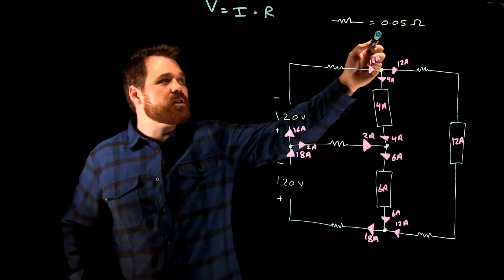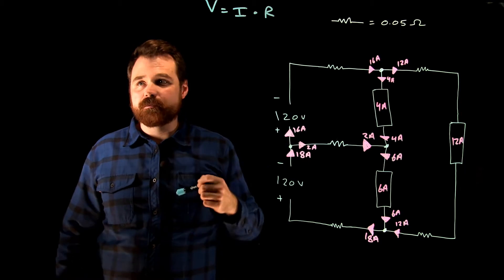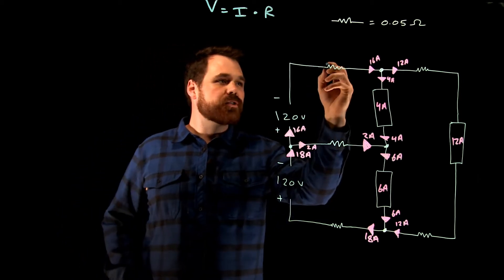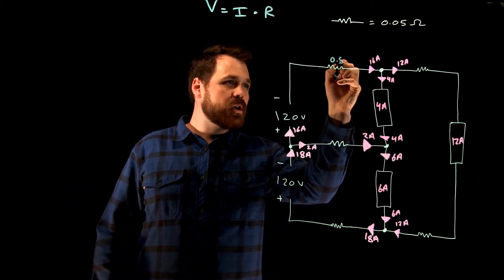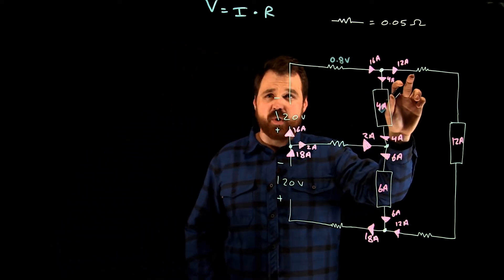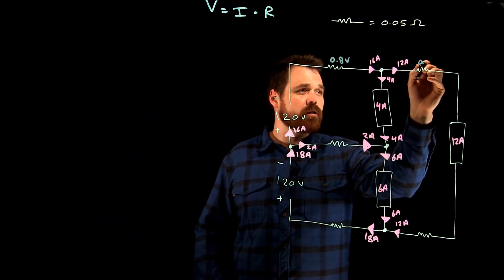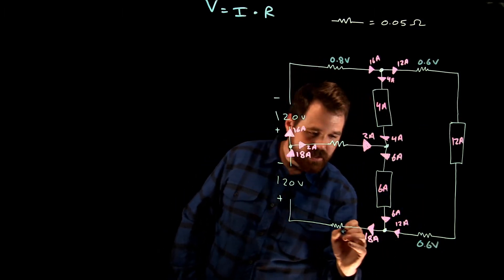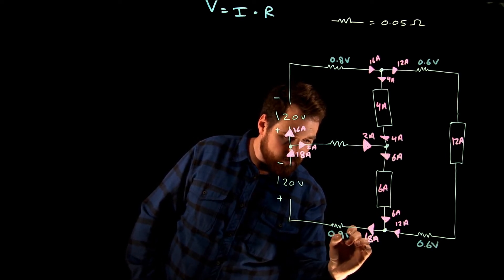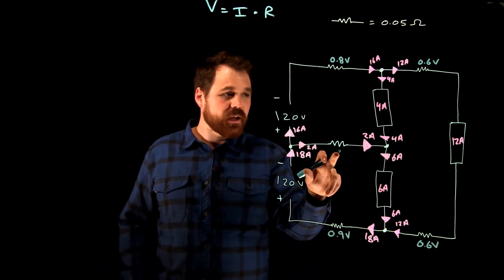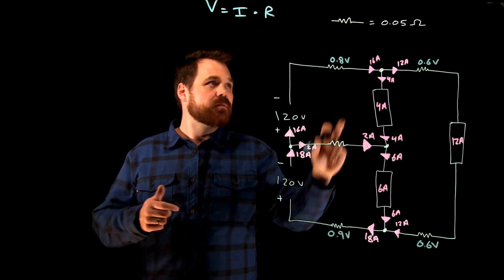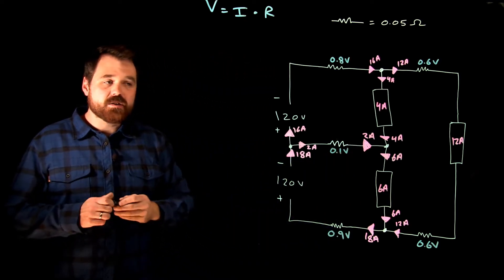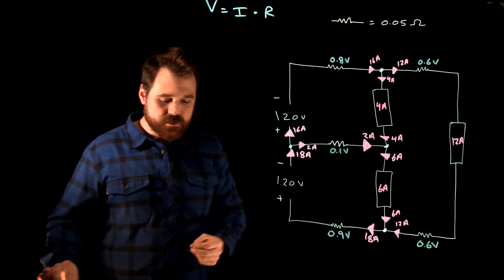We're going to say that each conductor is 0.05 ohms, and I'm going to go around and put all the voltage drops. Here I have 16 amps, which gives me a voltage drop of 0.8 volts. Here I have 12 amps, which gives me 0.6 volts. Again, 12 amps gives 0.6 volts. 18 amps gives me 0.9 volts. And here I had 2 amps — 0.05 ohms gives me 0.1 volts. That gives me all of my conductor voltage drops.